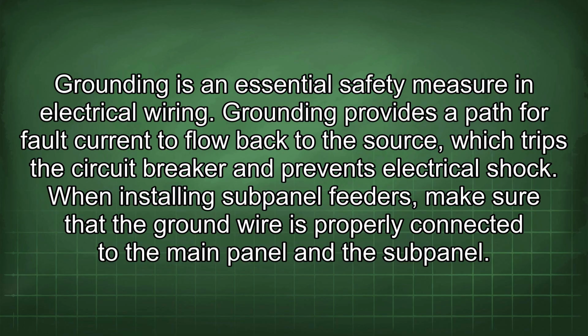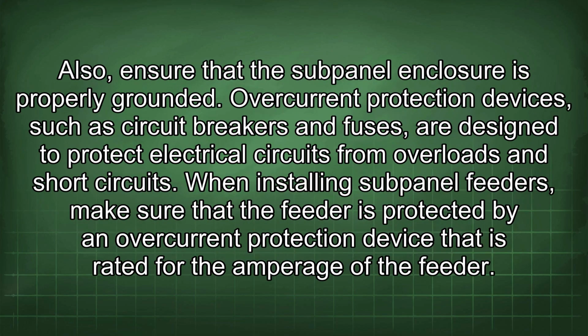Grounding is an essential safety measure in electrical wiring. Grounding provides a path for fault current to flow back to the source, which trips the circuit breaker and prevents electrical shock. When installing subpanel feeders, make sure that the ground wire is properly connected to the main panel and the subpanel. Also, ensure that the subpanel enclosure is properly grounded.